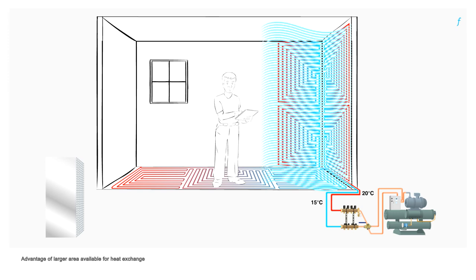Using heat exchangers in the form of chilled water carrying pipes embedded in floors or walls or ceilings or in panels ensures the availability of a much larger area for heat exchange compared to a regular heat exchanger which is impeded by space constraints. Sufficient cooling can be achieved with higher chiller operating temperatures, which in turn results in a higher coefficient of performance for the chiller and consequently lesser energy consumption.